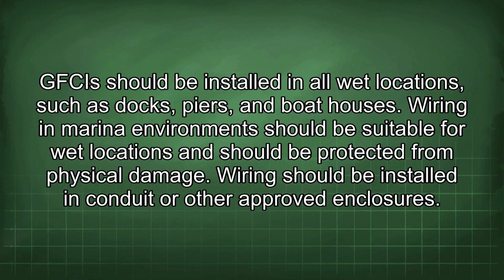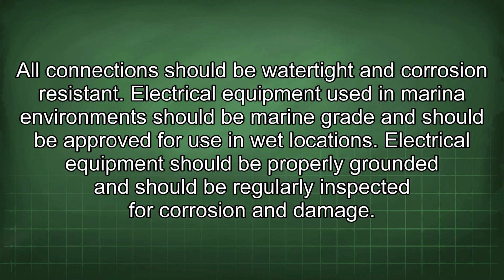Wiring in marine environments should be suitable for wet locations and should be protected from physical damage. Wiring should be installed in conduit or other approved enclosures. All connections should be watertight and corrosion resistant. Electrical equipment used in marine environments should be marine grade and should be approved for use in wet locations. Electrical equipment should be properly grounded and should be regularly inspected for corrosion and damage.